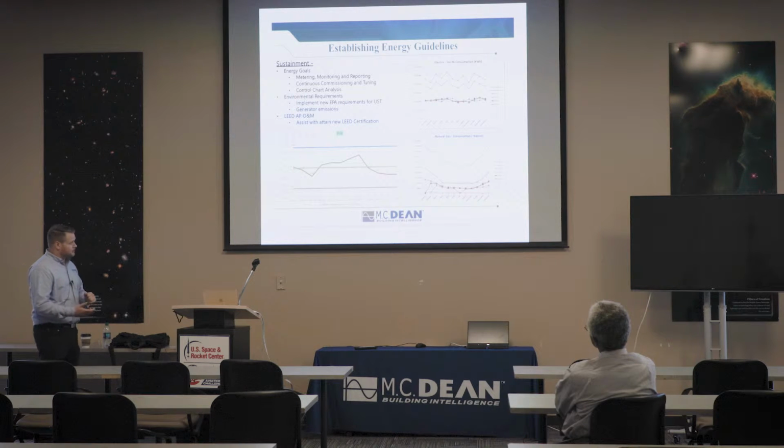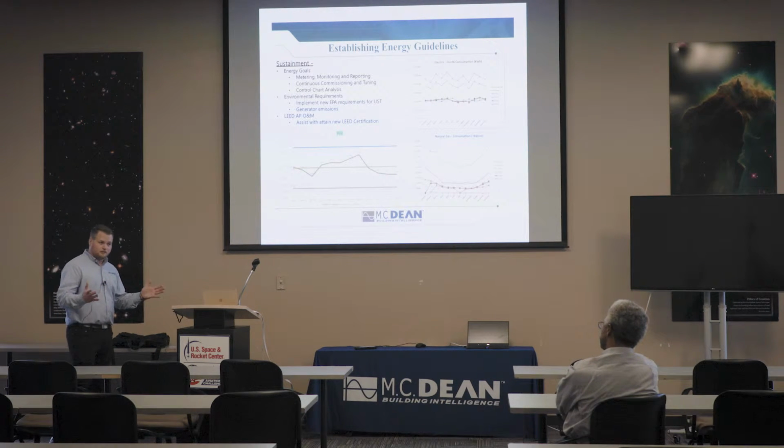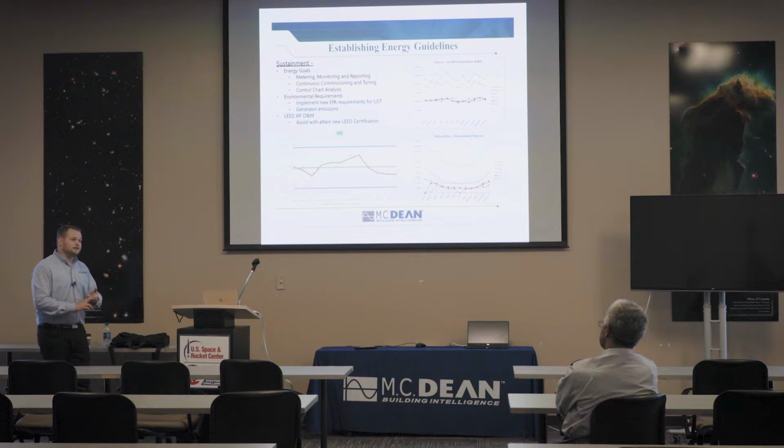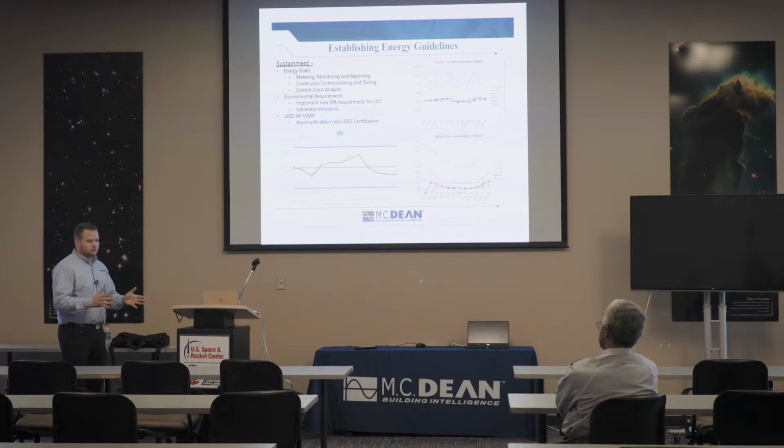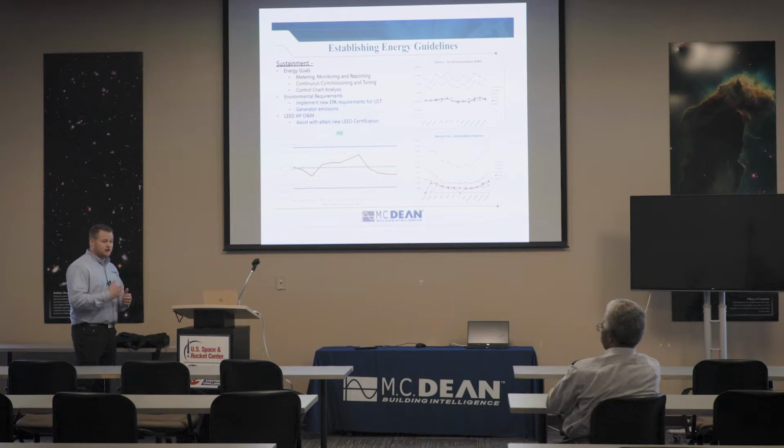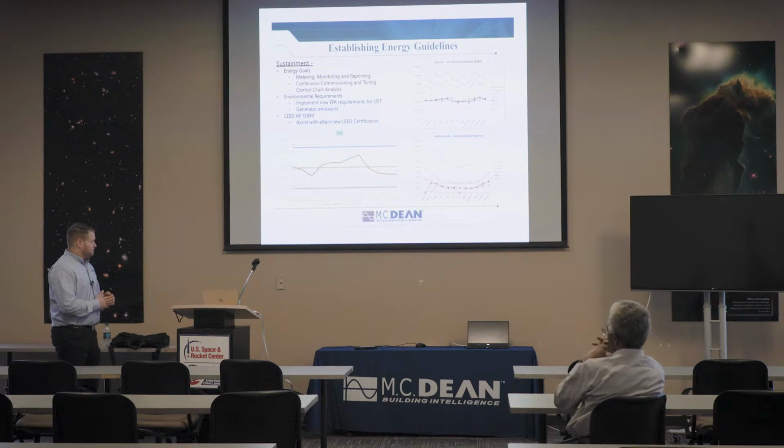So for a data center, the ideal in a vacuum mentality would be 1, because that means 100% of the power is going to your data center. But with cooling requirements, employees and operations, you're never going to get towards that. So anything under 2 is actually very good by energy standards. It's kind of the written rule there.